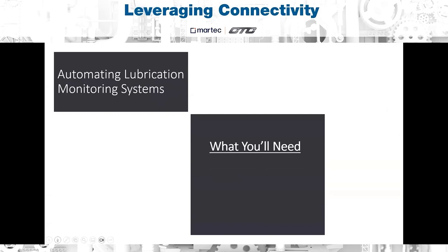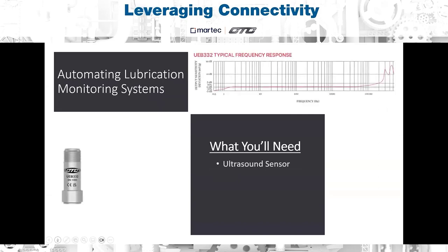You can actually go one step further with these signal conditioners to actually automate your lubrication system. This can be accomplished when pairing the conditioner with one of our UEB ultrasound sensors. This ultrasound sensor combines a linear vibration output of 0.5 hertz to 23 kilohertz, and it has a resonant peak of 42 kilohertz. This allows this one sensor to give a premium output in both the vibration range as well as the ultrasonic range. This is important because ultrasound is typically utilized for monitoring lubrication issues. So this is a perfect sensor that will allow you to do both.